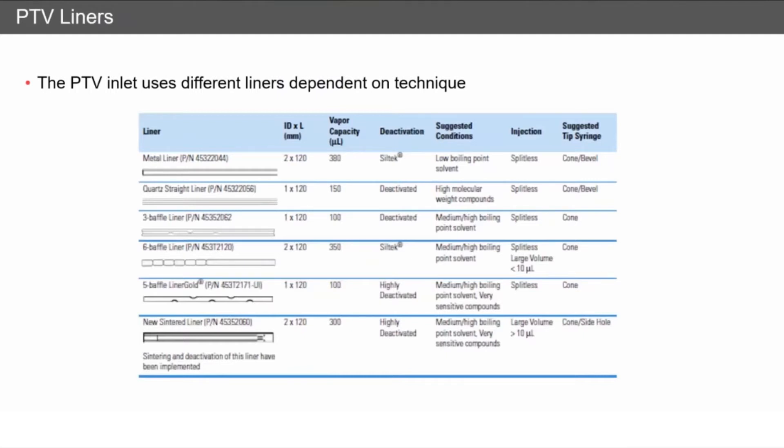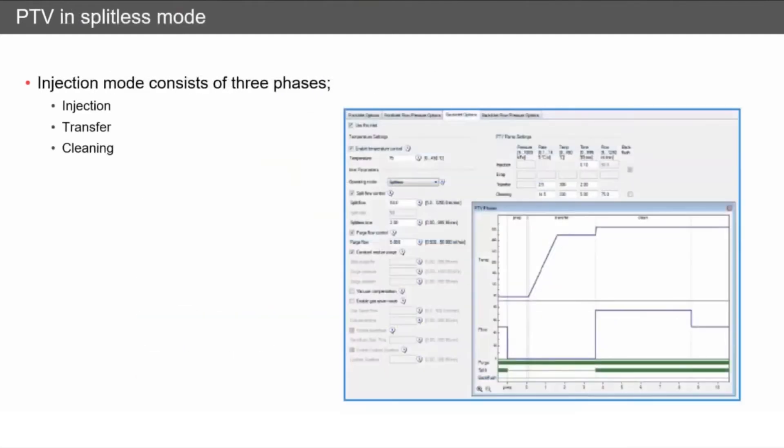The PTV can be used in a standard splitless mode. When it's used in splitless mode, it's slightly different to a split/splitless inlet. The injection consists of three phases: an injection phase, a transfer phase, and a cleaning phase.